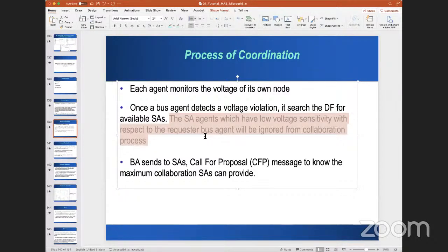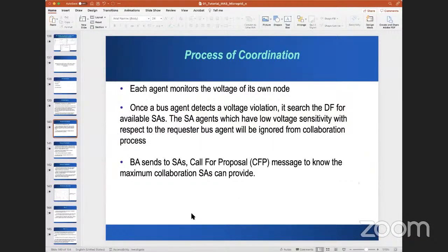So you have to study the system to decide whether it's really going to help, because sometimes when you make a change, you might create a violation on another bus. This is because as soon as you inject reactive power into the system, you are basically increasing the voltage everywhere you are influencing. So it's very important to study the system.